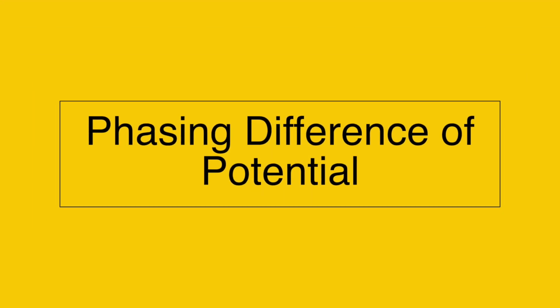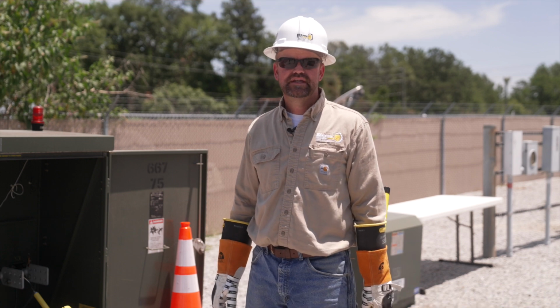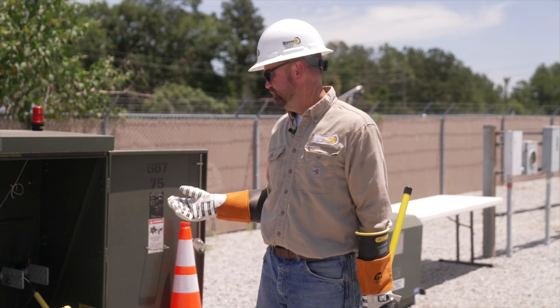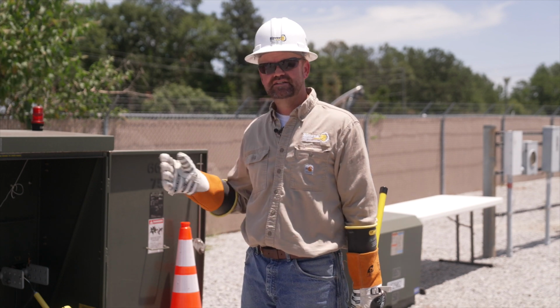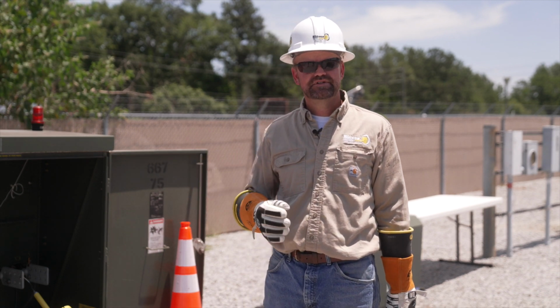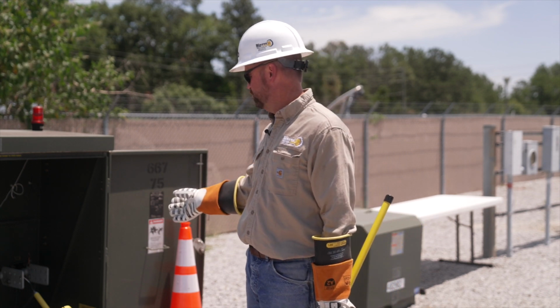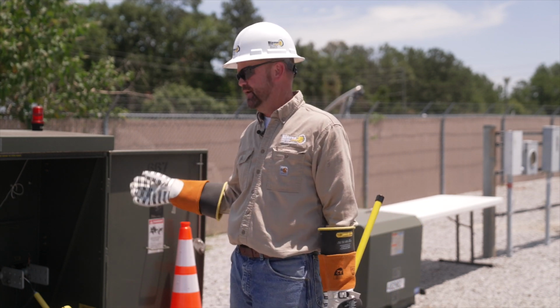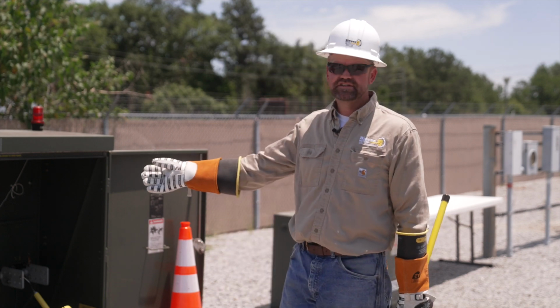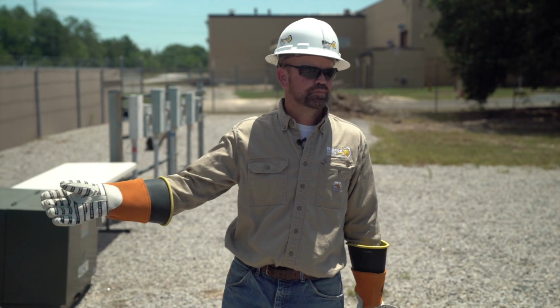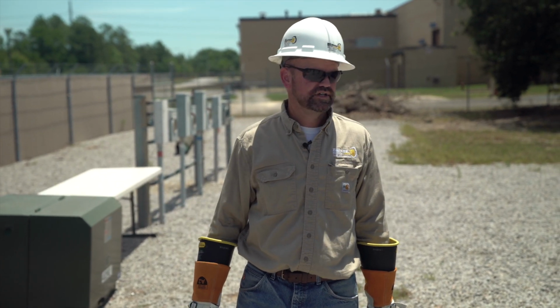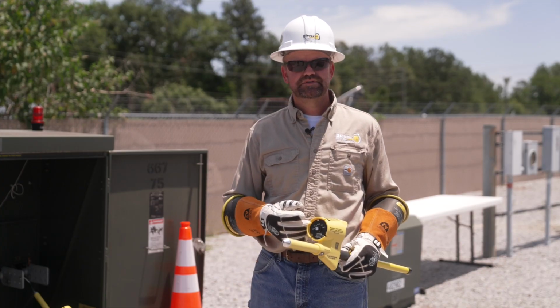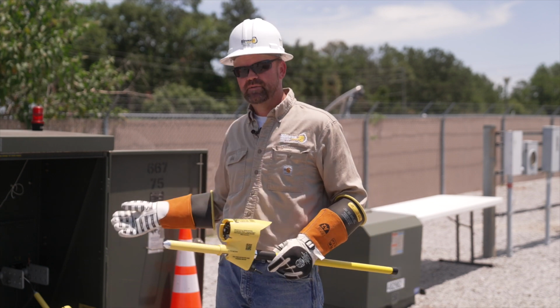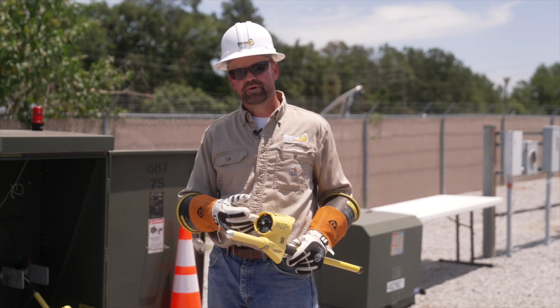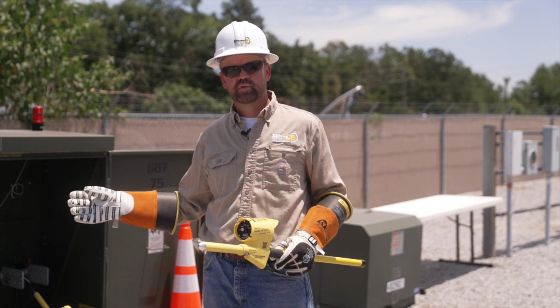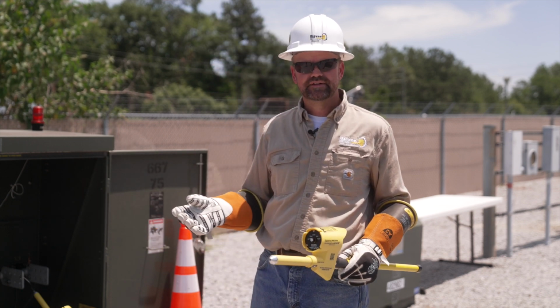The next demonstration will be phasing difference of potential. So at the beginning of this demonstration, I talked about the unique feature with this device is phasing difference of potential rather than the same potential. So here I have my reference probe on my X2 secondary bushing, and now I'm going to take my meter probe and go over to one of these capacitive test points and determine which primary is the source of this X2 bushing. I have both devices in the DEG switch position. I have my reference probe hanging on my X2 bushing, and now I'll take my meter probe and start touching each capacitive test point until I get a 0 or near 0 reading.